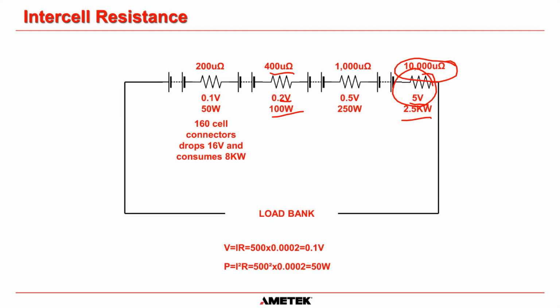sure that your battery is going to give you the capacity you need, and that these intercell connections aren't going to heat up. Because I've seen many pictures where batteries have started to explode or melt because these intercell connections heat up so much, and they can ignite the hydrogen inside the battery. Obviously not so much for valve regulated cells, but for wet cells. So it's extremely critical that you make sure the intercell connection resistances are measured correctly by making sure your probe is on the post and the following post, and that everything is tight and looks good.